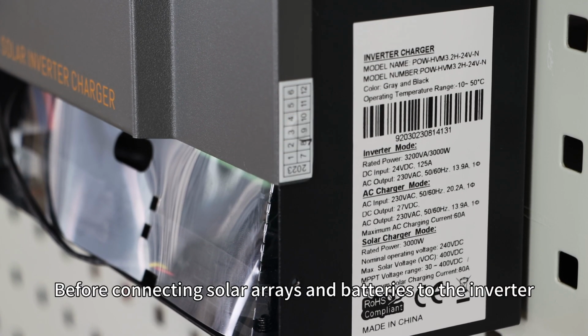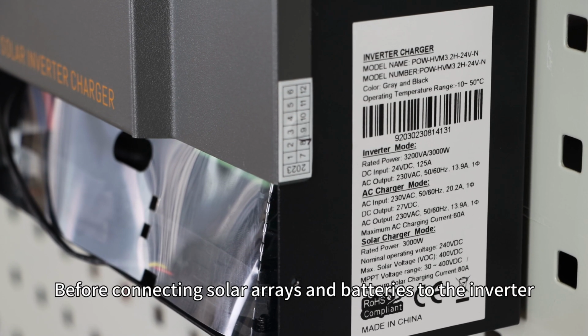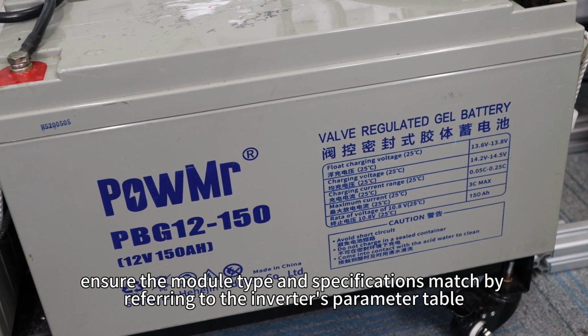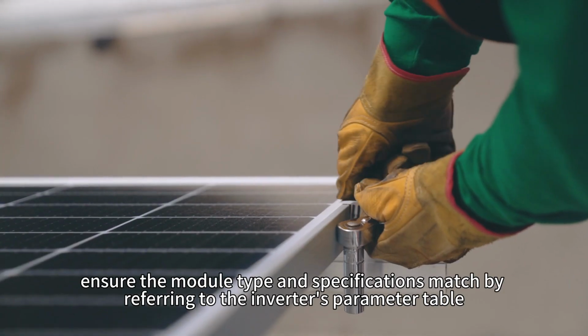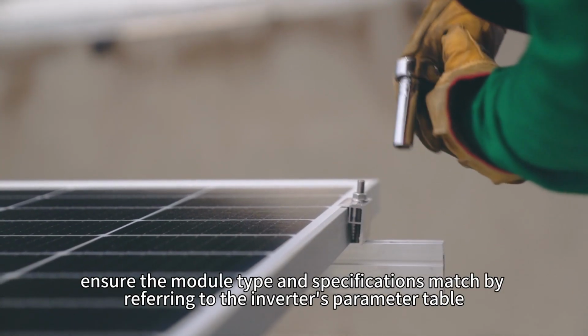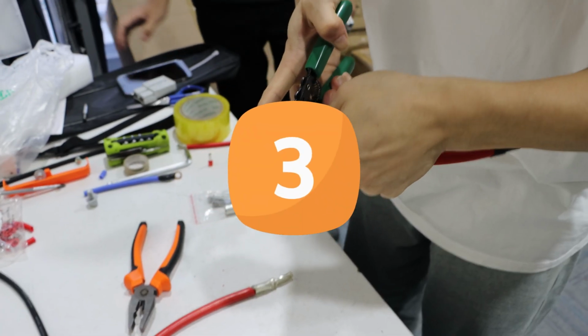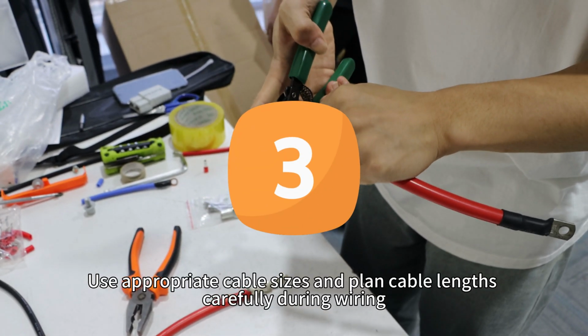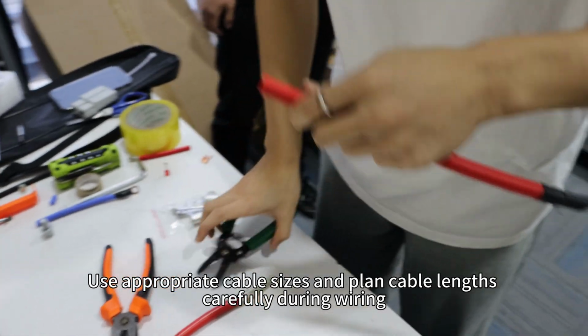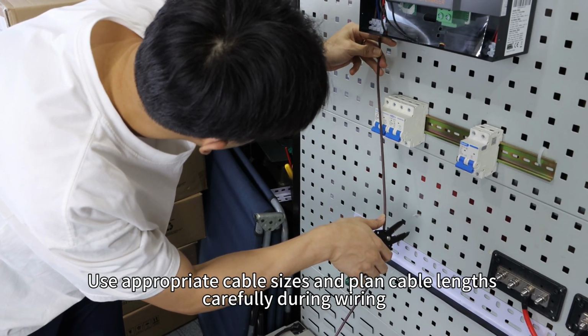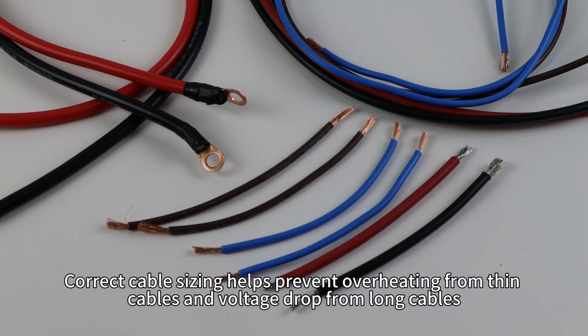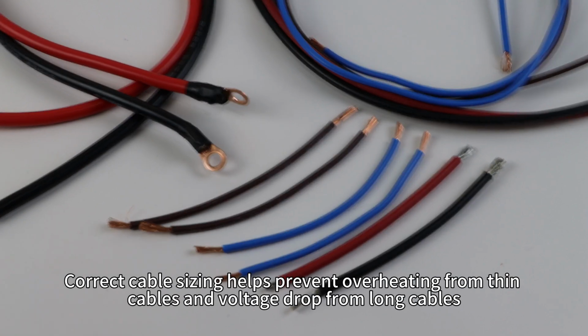Before connecting solar arrays and batteries to the inverter, ensure the module type and specification match by referring to the inverter's parameter table. Use appropriate cable sizes and plan cable lengths carefully during wiring. Correct cable size helps prevent overheating from thin cables and voltage drop from long cables.